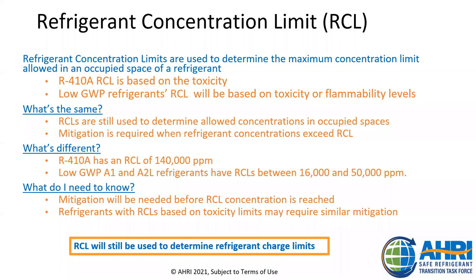R410A has an RCL of about 140,000 parts per million, and most of you already know that. Low GWP A1 and A2L refrigerants have RCLs between 16,000 and 50,000. So what do you need to know? Well, we really need to know that mitigation will be needed before the RCL concentration is reached, and refrigerants based on toxicity limits that have lower RCLs may also require similar mitigation. But bottom line, the RCL will still be used to determine the refrigerant charge limits.